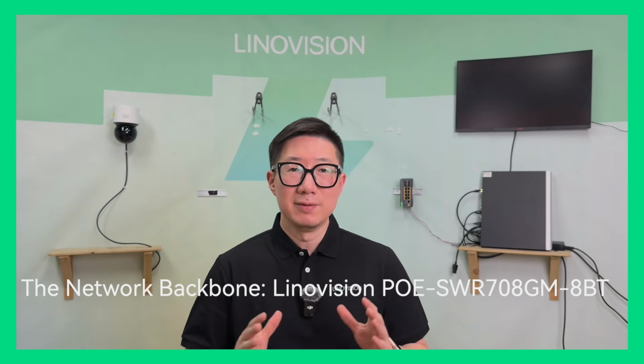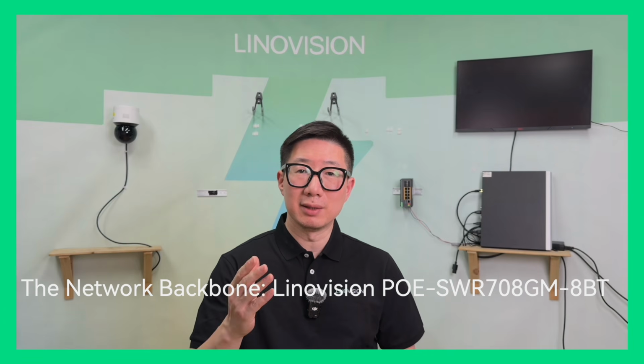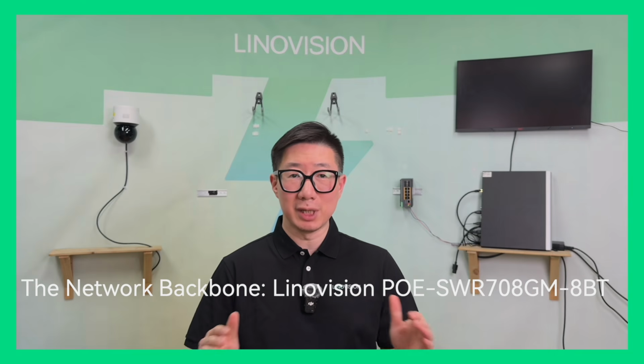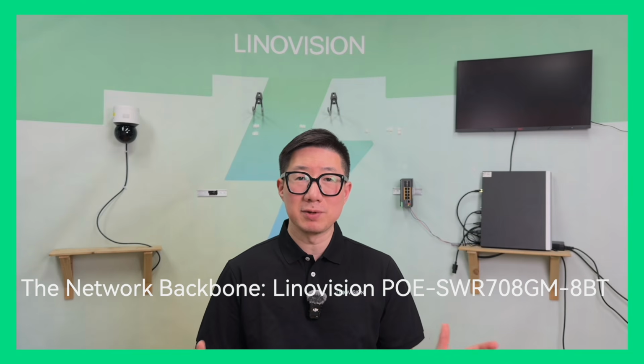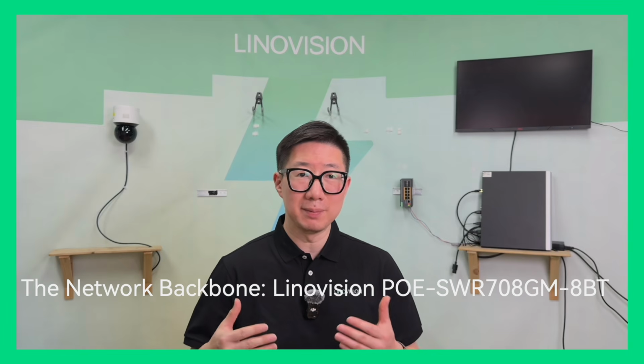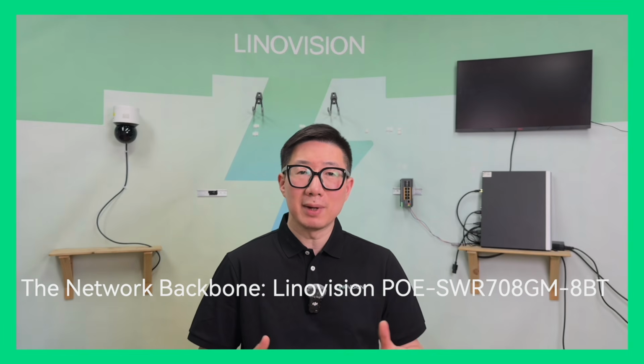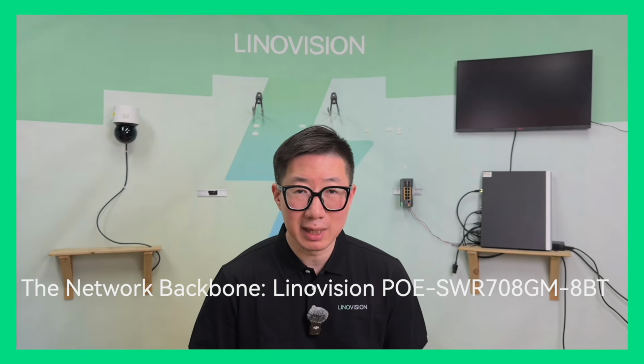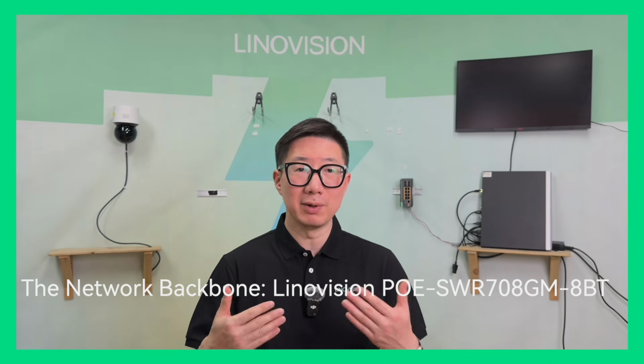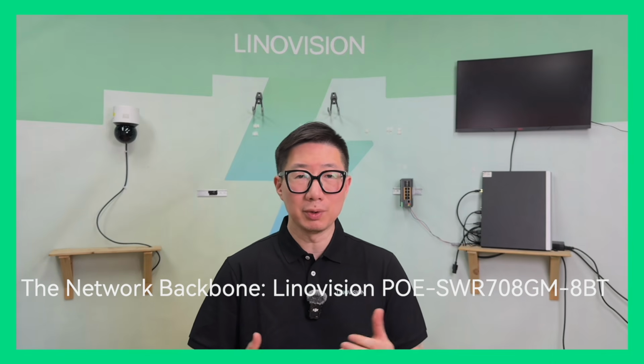For lighting, VLAN segmentation means you can isolate the lighting network from the general IT traffic, which is both a security best practice and a reliability consideration. QoS gives you the ability to prioritize control traffic, and remote access means changes don't require a site visit.